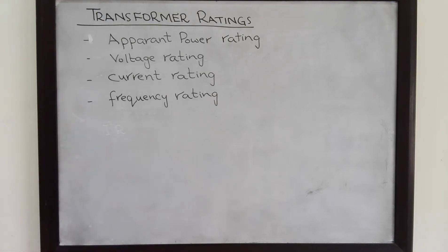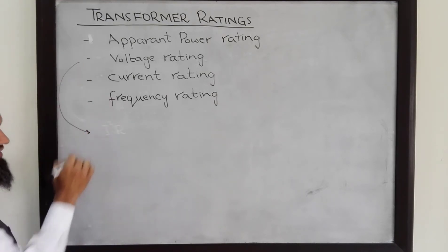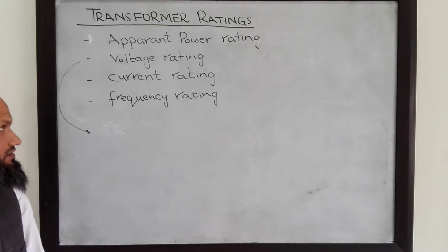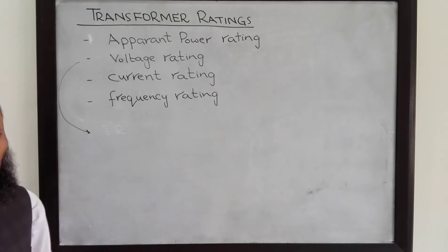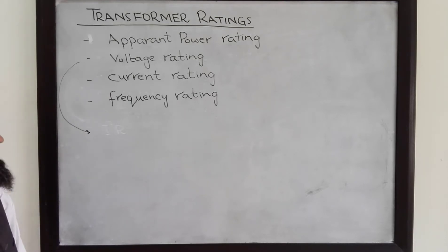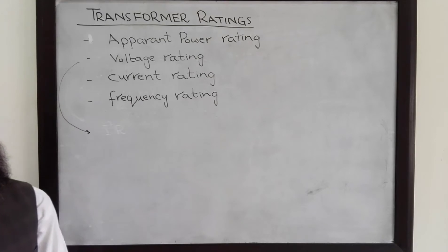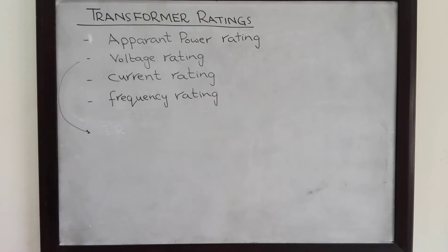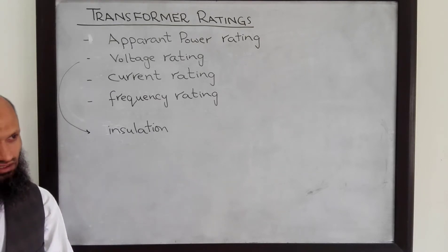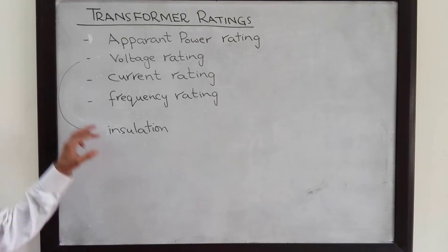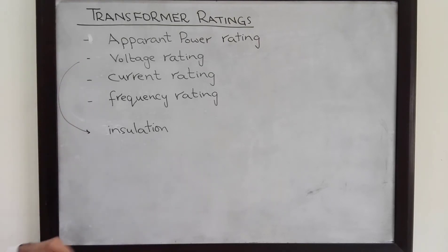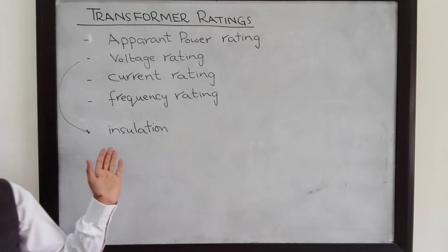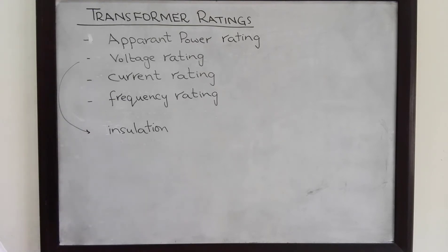Another important rating is the voltage rating. The maximum voltage that can be applied to the transformer is also limited. The first aspect is insulation. The windings that are there on the transformer and also the insulation among the windings, that is designed to handle a certain maximum voltage. Therefore, we cannot apply a voltage higher than that particular voltage, because that will damage the insulation and hence will damage the transformer. This is one aspect.